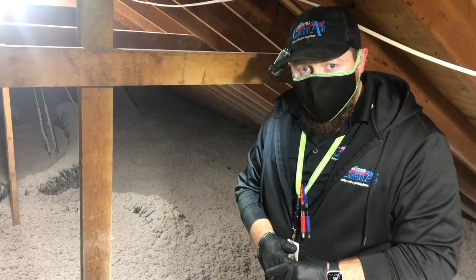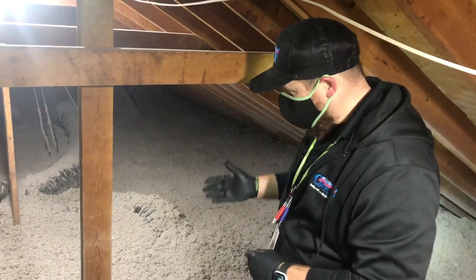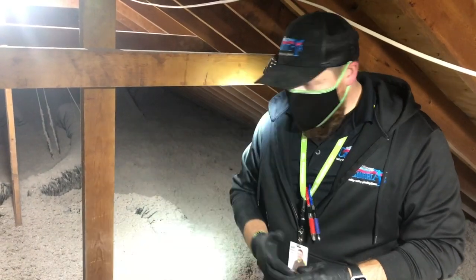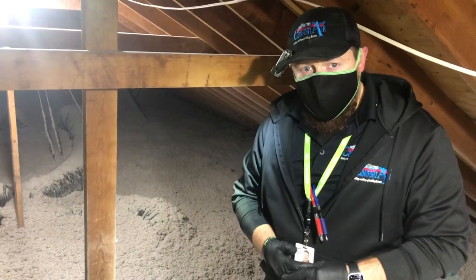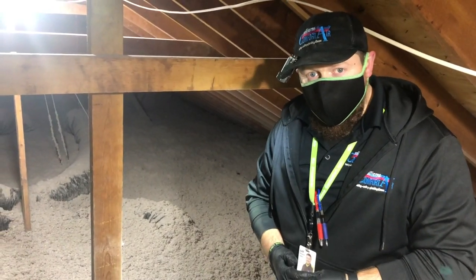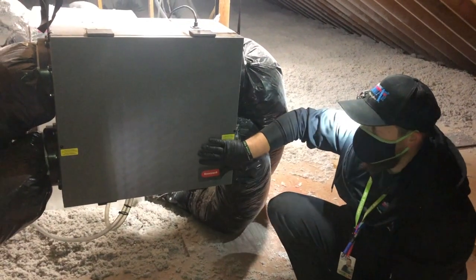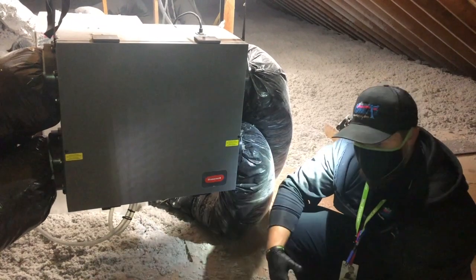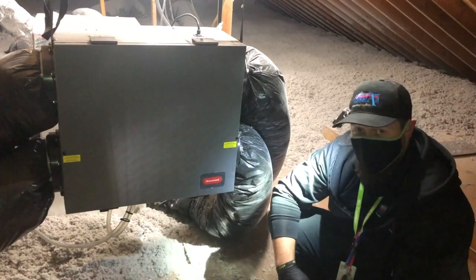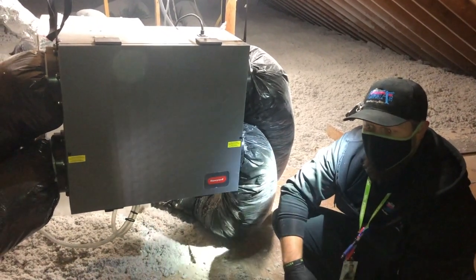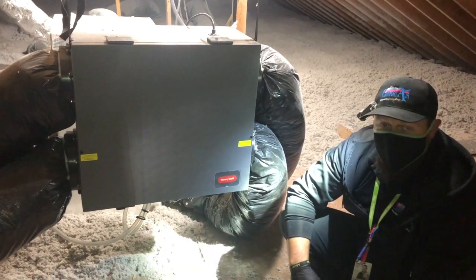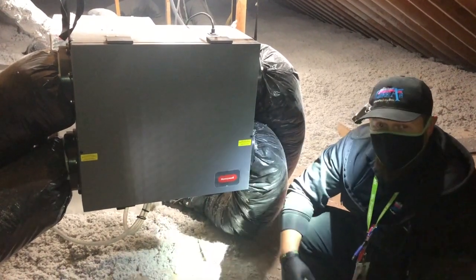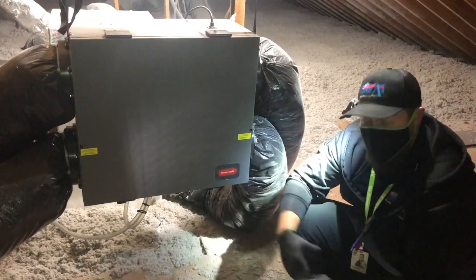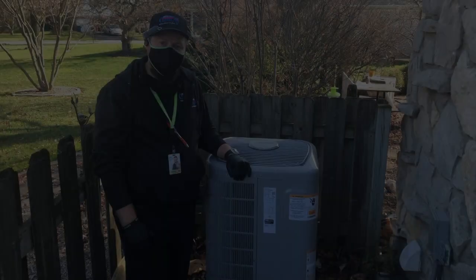We did that with a 2-part closed cell spray foam. Once we were done, and we verified we were done, we were able to come back in and do a blown-in cellulose back to an R38 value. So we also put in our energy recovery ventilator to help the house breathe and bring in the good air, the fresh air that we wanted to breathe, and not the contaminated air that we were once getting from all the top plates and openings within the home that were infiltrating into the home.